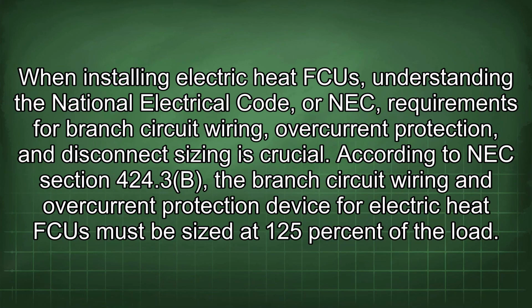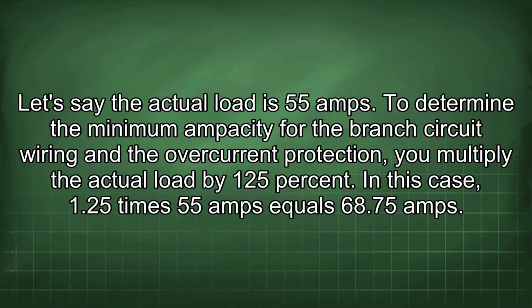When installing an electric heat FCU, understanding the National Electrical Code, or NEC, requirements for branch circuit wiring, overcurrent protection, and disconnect sizing is crucial. According to NEC Section 424.3(B), the branch circuit wiring and overcurrent protection device for an electric heat FCU must be sized at 125% of the load. Let's say the actual load is 55 amps.